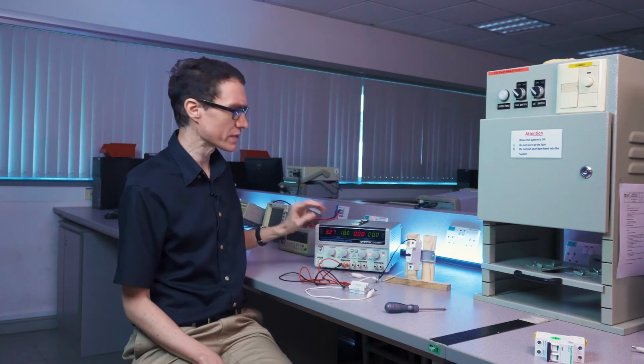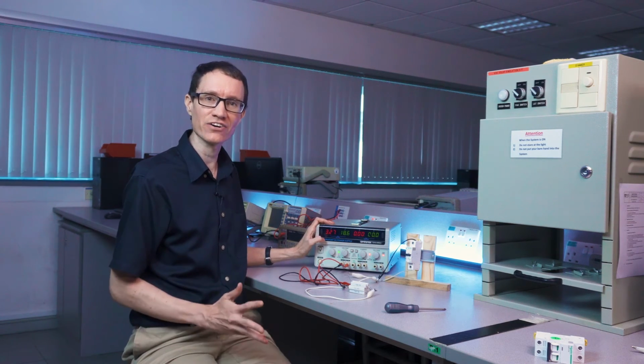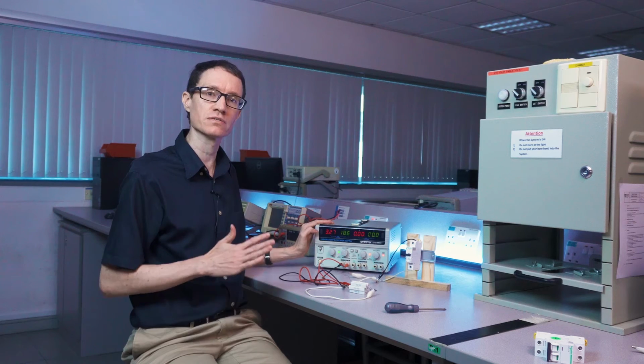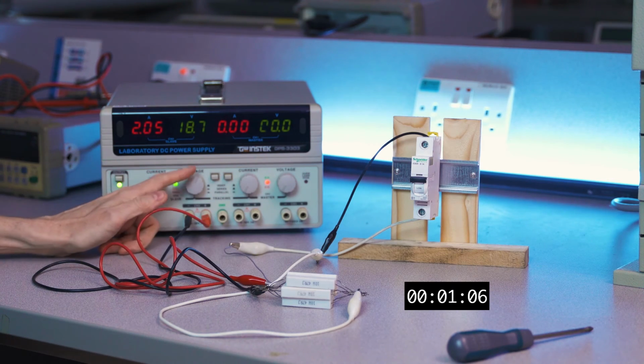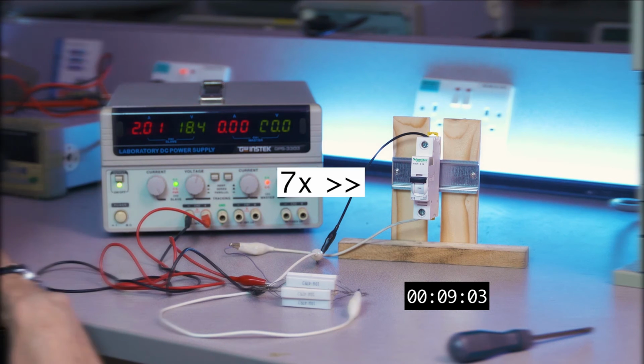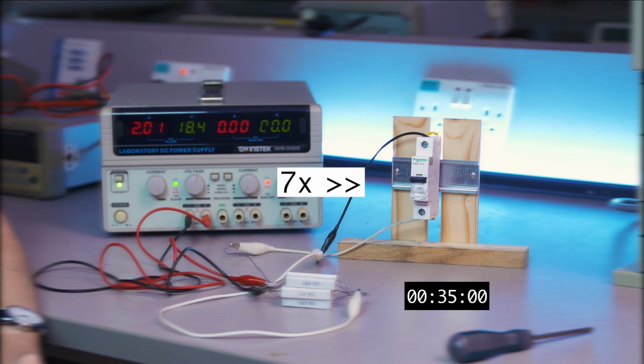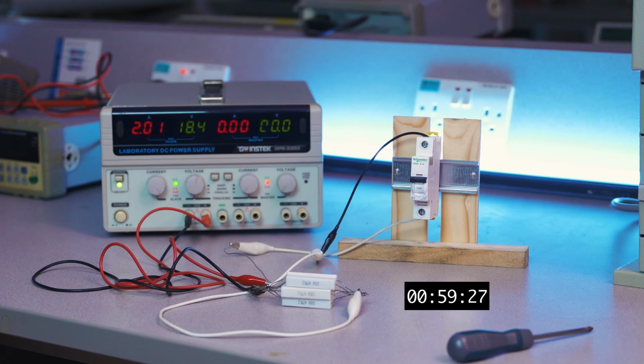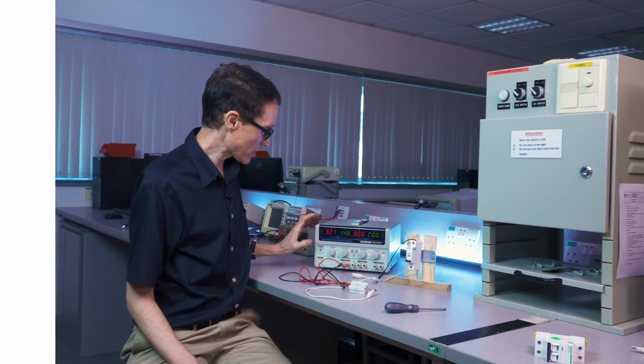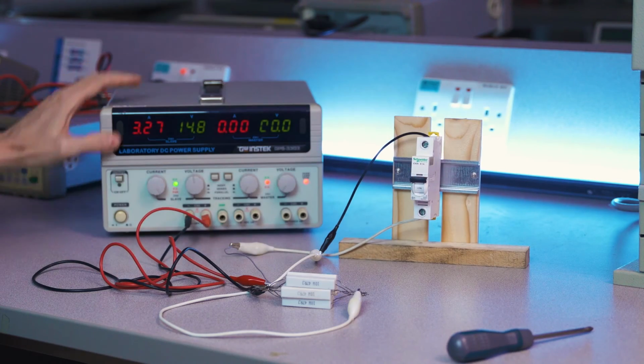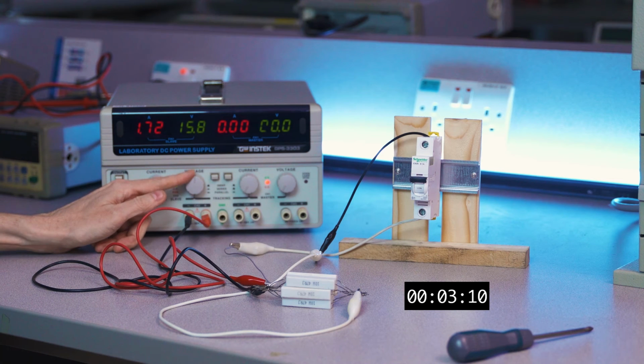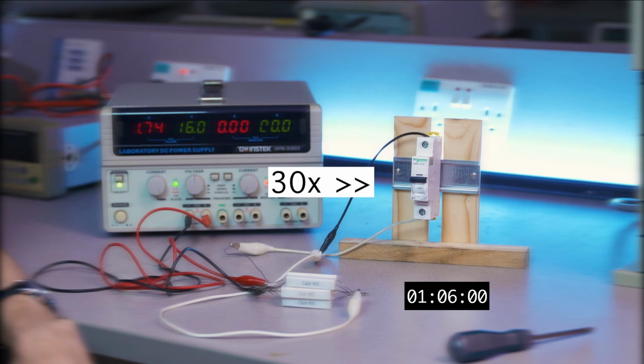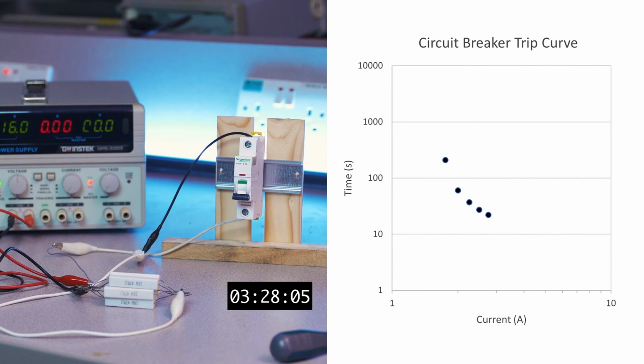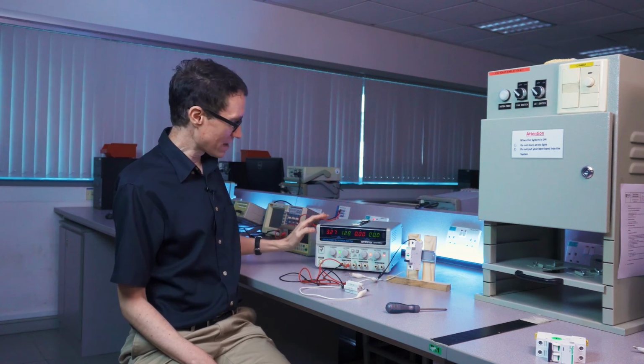We're mostly in the thermal tripping region at this point. This power supply can't really give us the high currents that we need in order to get into the magnetic tripping region, so our curve is mostly going to be in the thermal region here. Let's try 1.75 amperes. It's taking a bit longer to trip now. Let's go to 1.5 amperes and see how long it takes.